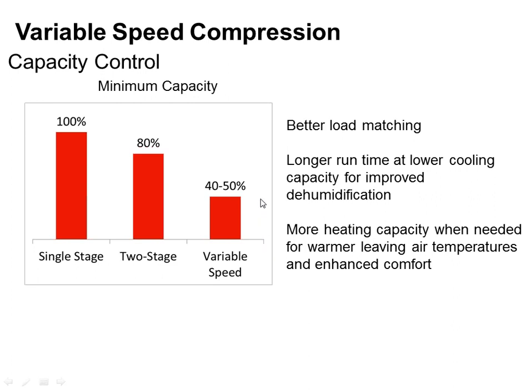These variable speed heat pumps, they can ramp down from 100 down to 40%. I forget exactly which ones. It's the 3 and 5 ton size, I believe, that goes down to 40, and the 2 and 4 ton size go down to 50. But they can ramp down as far as 40%, and they operate in 1% increments. So a 3-ton heat pump would go from 40 to 100% in 1% increments. So 40, 41, 42, 53, 79, whatever. It's basically a 61-stage heat pump if you want to think of it in stages. From 40 to 100 in 1% increments is 61 stages, plus 0, obviously. So we get much longer run time. If we can keep things running, it keeps the evaporator indoor coil wet, which keeps us dehumidifying longer.